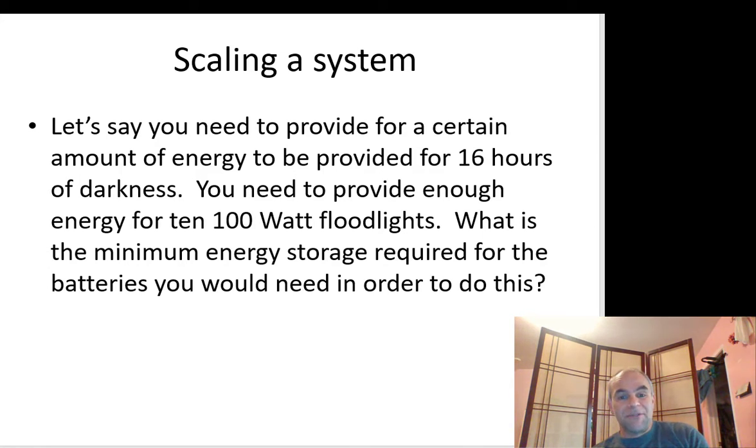And so let's determine the minimum energy required for this, and then we'll go from there to figure out how many solar panels we'll need in order to make sure that the battery is full at the beginning of each evening period. So the first step is to determine the amount of energy that's required. So 10 100-watt floodlights means that you're consuming 10 times 100 or 1,000 watts, which is a kilowatt, and that you need to be able to provide that energy for 16 hours. So that's 16 kilowatt hours.